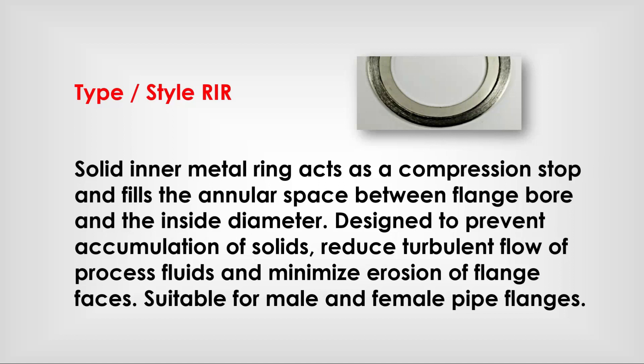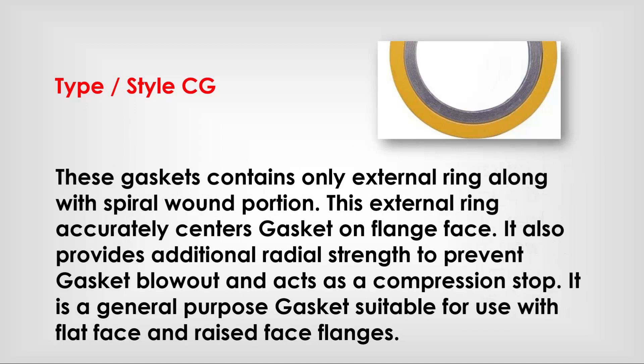Type style with inner ring: a solid inner metal ring acts as a compression stop and fills the annular space between the flange bore and the inside diameter. This design prevents accumulation of solids, reduces turbulent flow of process fluids, and minimizes erosion of flange faces. Suitable for male and female pipe flanges.